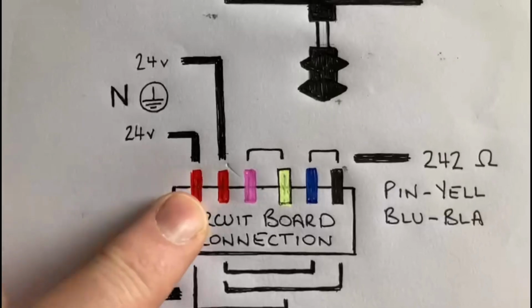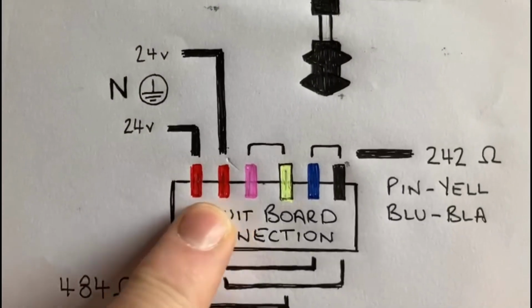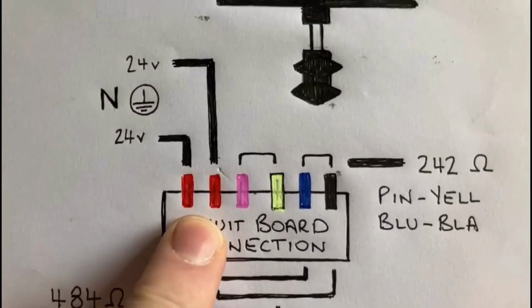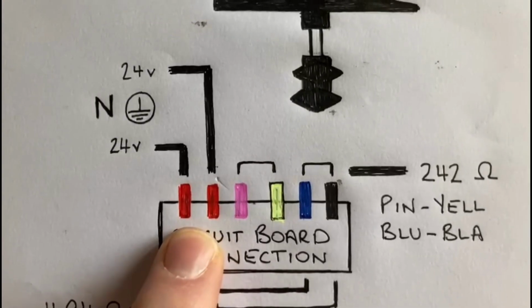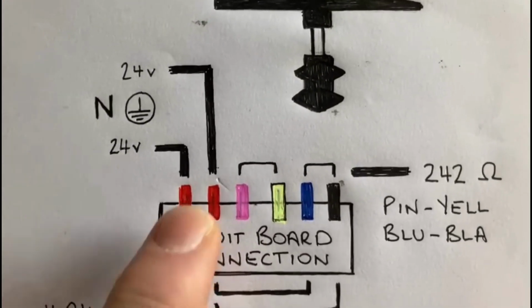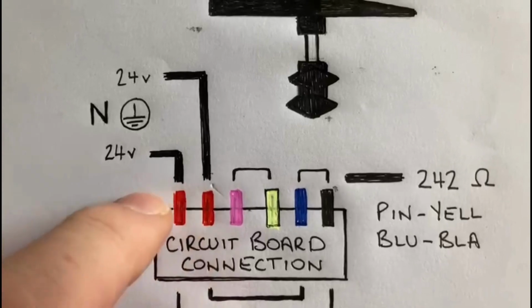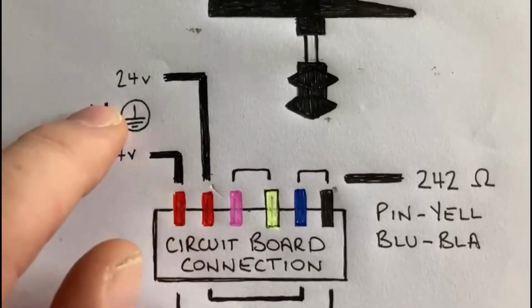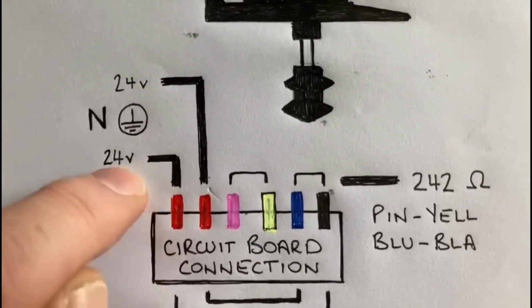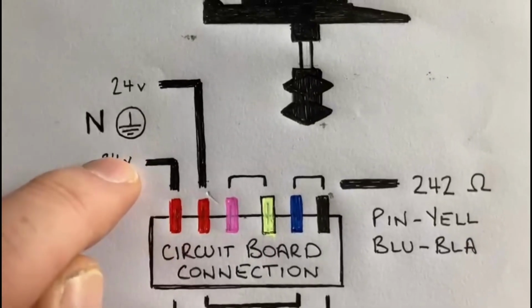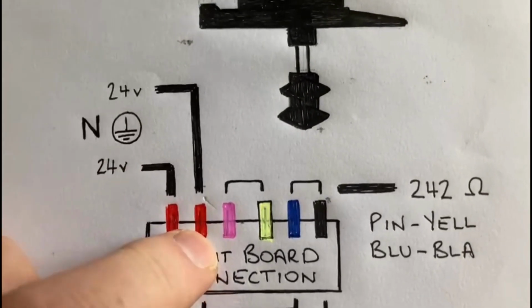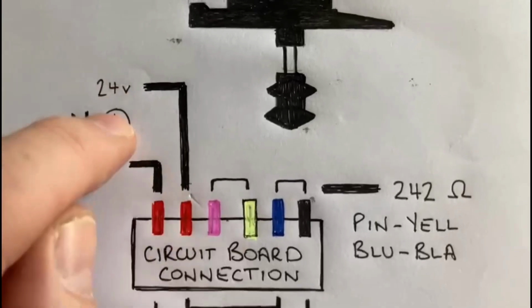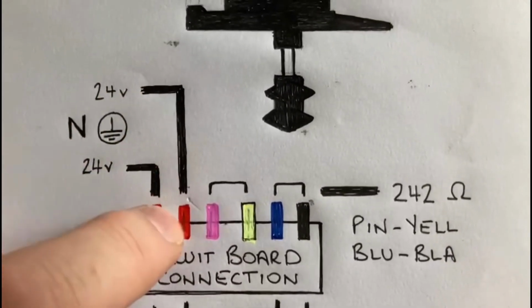So the 2 left red connections are your 24 volt power connections from the circuit board. So if you test any of these, if you test red to neutral or red to earth, you'll get 24 volts on this one. And then the same again on this one. Test red to neutral or red to earth, you'll get 24 volts on this one.